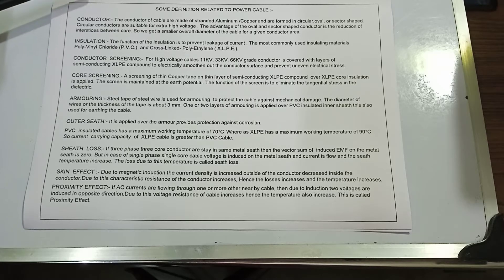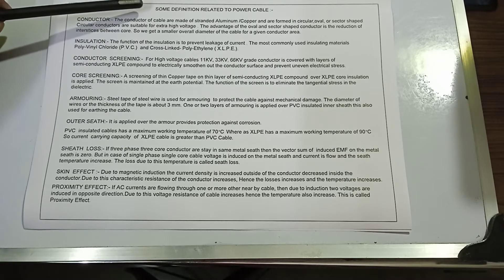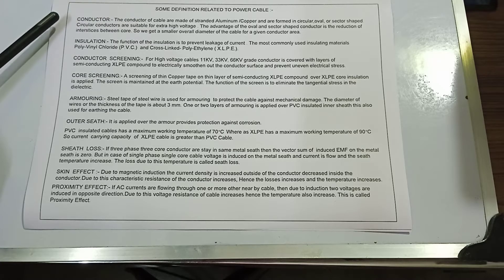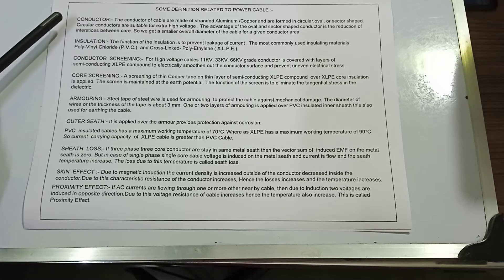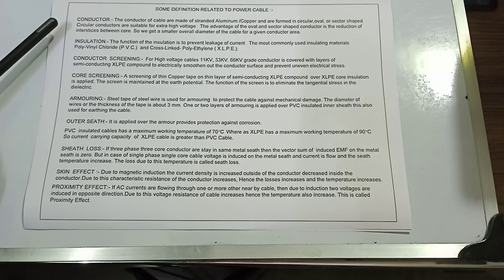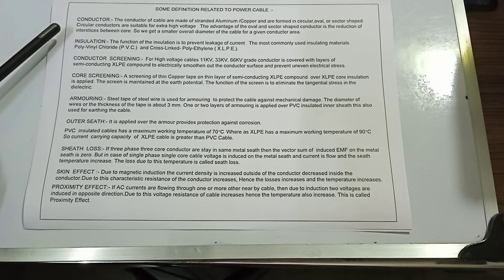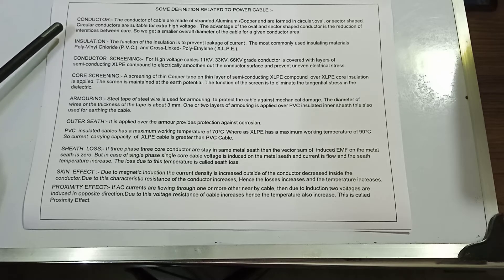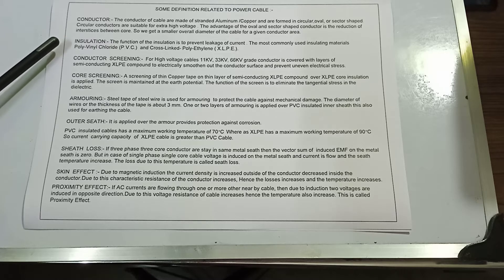Now I am going to discuss some definitions related to power cable. First: conductor. The conductors of a cable are made of stranded aluminium or copper and formed in circular, oval, or sector-shaped profiles. Circular conductors are suitable for extra high voltage. The advantage of oval and sector-shaped conductors is the reduction of interstices between cores.